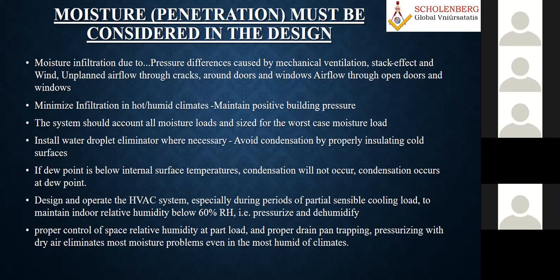Similarly, dew point temperature, you have to be very, very careful about that. I also mentioned that on that day: if you are maintaining your surface temperature below the ADP, definitely condensation will come. Condensation occurs means it's another issue of moisture growth. The moisture will definitely allow fungus and mold to grow. So this type of thing you have to definitely look into.